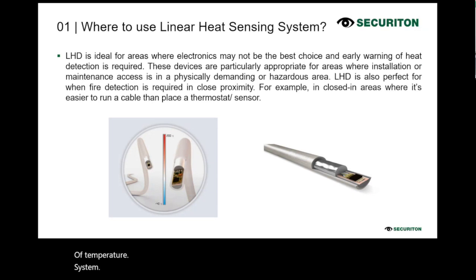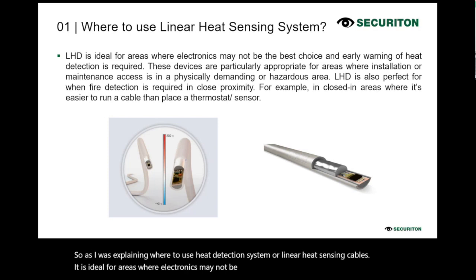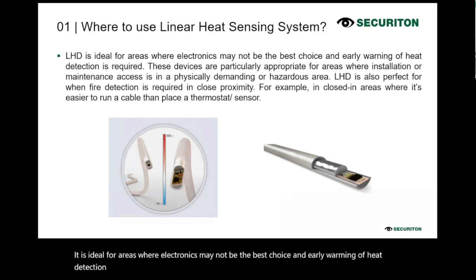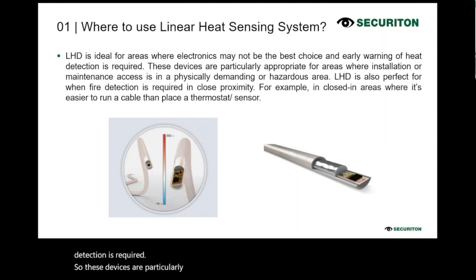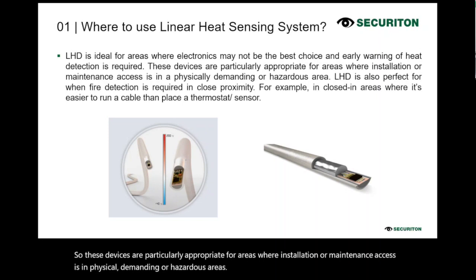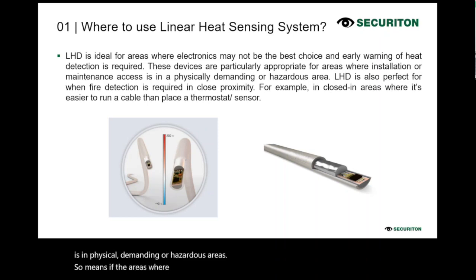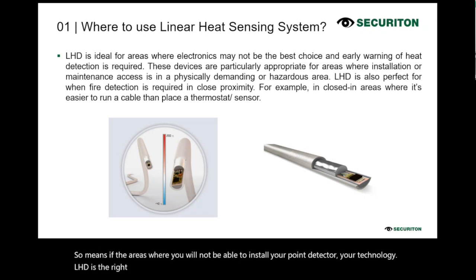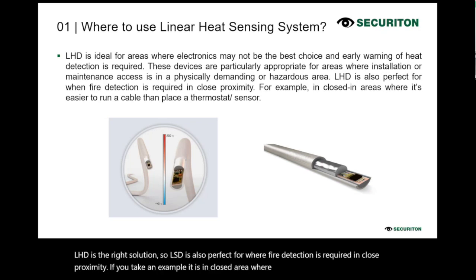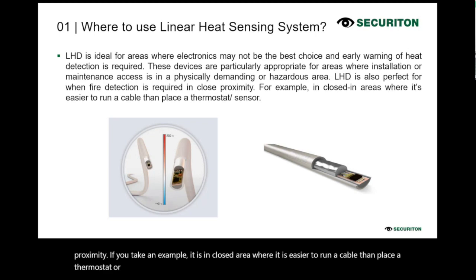As I was explaining where to use heat detection systems or linear heat sensing cables, it is ideal for areas where electronics may not be the best choice and early warning of heat detection is required. These devices are particularly appropriate for areas where installation or maintenance access is physically demanding or hazardous. So if there are areas where you will not be able to install your point detector, LHD is the right solution. LHD is also perfect where fire detection is required in close proximity. For example, in a closed area where it's easier to run a cable than place a thermostat or sensor, meaning the other heat sensing devices.